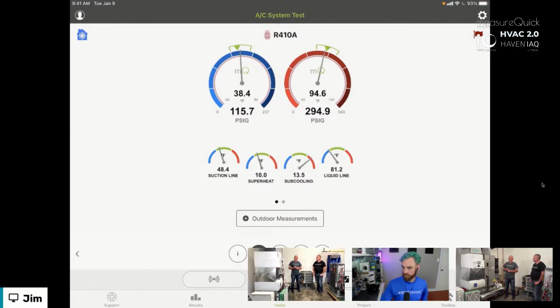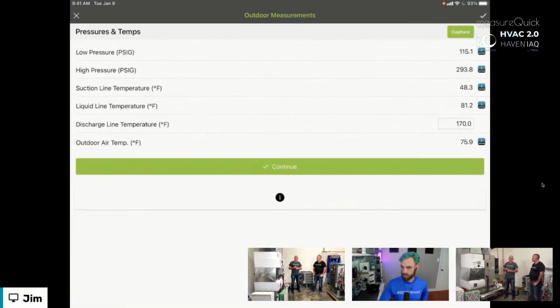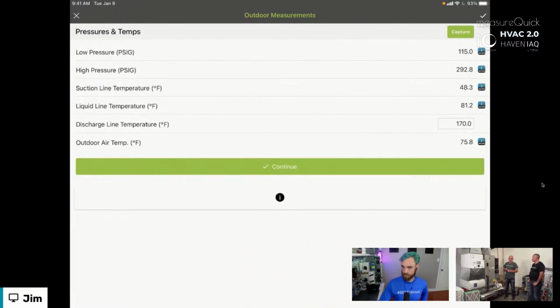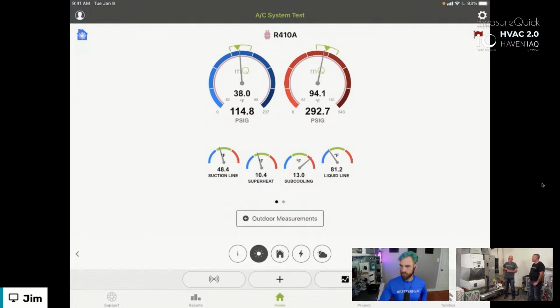And so you'll see on there, when you're looking at that, we're running some pretty interesting sensible latent splits. Last time I looked, it was about a 0.58 sensible latent split, meaning that 58% of the energy we're using is for cooling the air, and the balance of the energy is for dehumidification. So we're pulling a lot of water right now on this system, and it's pretty common. We got a lot of textiles in here. We got all the ceiling tiles in here, so it's going to take a little bit of time to get this all dried out and running.